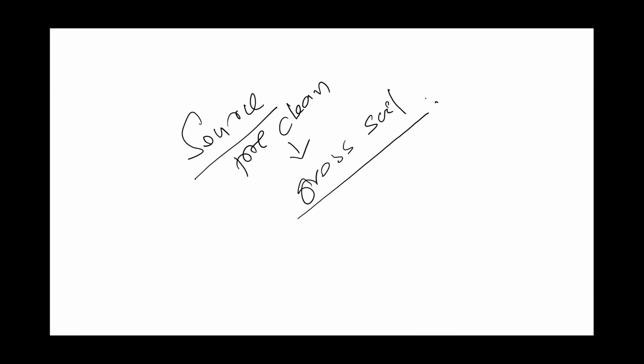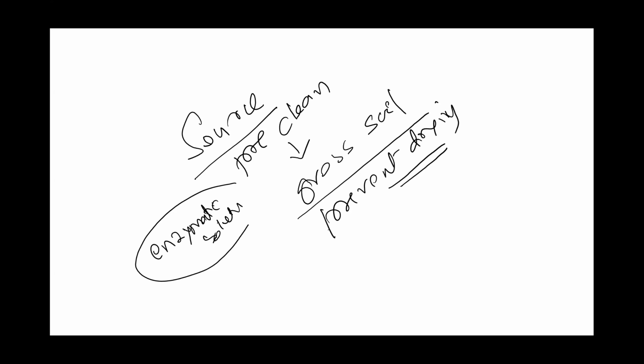Pre-cleaning at source means it will only remove the gross soil from the instrument by wiping, so that it prevents drying. The aim is to prevent the drying step. It can be done by soaking or spraying the instrument with an enzymatic solution. However, it should not be considered a standalone practice to replace cleaning at CSSD. Cleaning at CSSD is a mandatory process which cannot be replaced by pre-cleaning at the point of source.